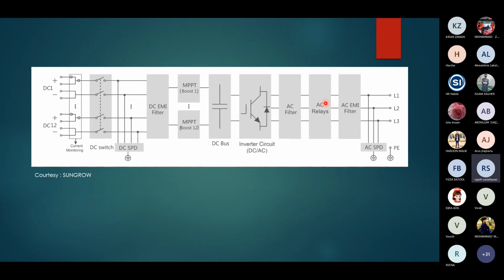But you can see that there is an AC relay also. Why do we need an AC relay? These inverters are not exclusively manufactured for one country, let's say. It is applicable for different countries. And the relays are also a protection device inside, because if the phase-to-phase voltage has an anomaly, or if the phase to neutral or the neutral to ground, or wherever it is monitoring, has a problem, then this relay immediately desyncs the inverter and protects itself. And suppose there is a high voltage on the AC side, then it cannot pump in the energy, right? So it again desynchronizes. So this is a protective device inside. And of course, as I explained, the EMI filters are like a correction device to give as pure a sine wave as possible. And also the AC side has a surge protection device.